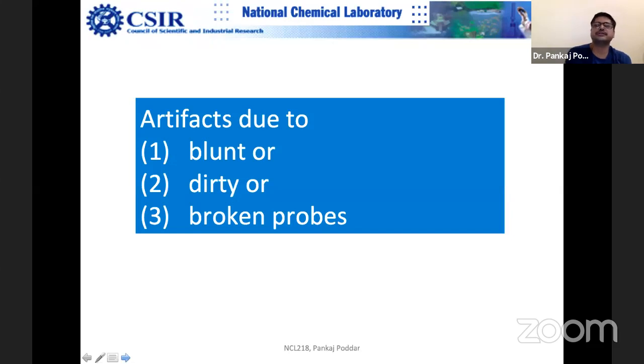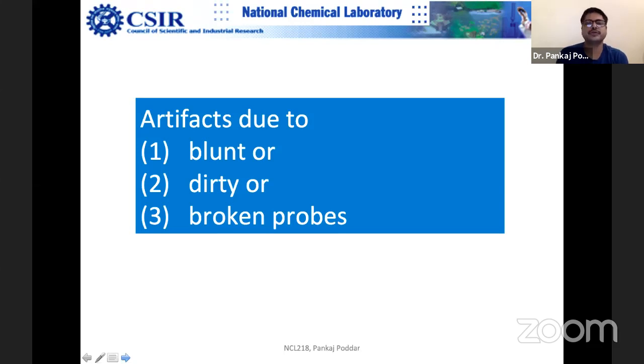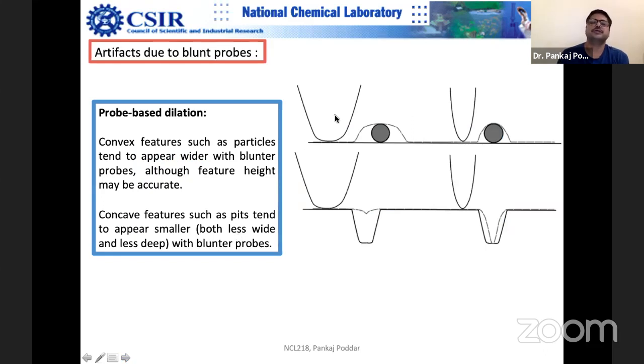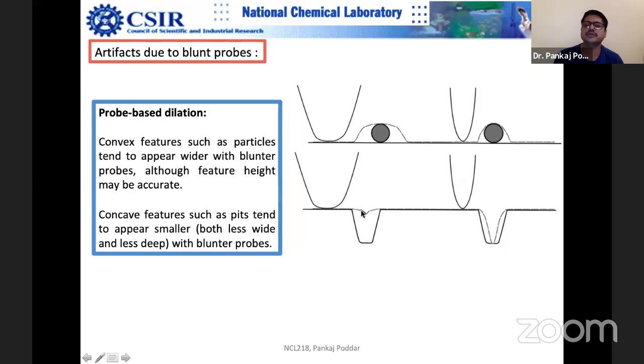Next topic: not just aspect ratio, sidewall, or angle, but what if the tip itself becomes blunt? The tip is like a pencil that can get dirty, broken, or get blunt. One tip can sometimes become two tips. If you started with a very sharp probe and the tip became blunt, for protruding features you can have significant convolution, and for valleys you can have imaging problems. The lateral resolution is affected, though you still get the same height measurement.